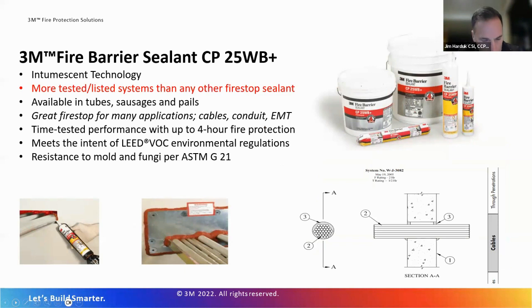As I'd mentioned before, 3M manufactures a few different types of fire stop sealants. The CP25WB is our workhorse of the product line. It is an intumescent sealant. We have more UL tested systems with this sealant than any other sealants in our product line. It's available in a couple different packaging sizes. It's available in the sausage packs and of course pails and tubes as well. This product, we have tested systems up to 4 hours. And if you're working on any projects that require LEED certification, we do have some credit points that you can qualify for with this product. Next slide.